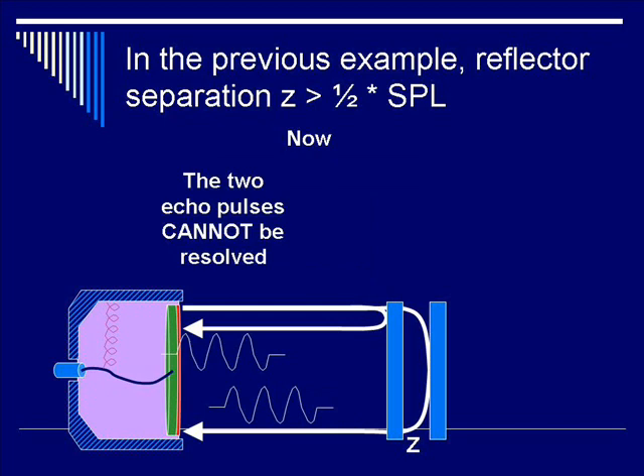And since there is overlap between the two pulses when it gets back to the transducer, the conclusion is that the two echo pulses cannot be resolved and therefore the two reflectors separated by the spacing z cannot be resolved because z is less than SPL over 2.